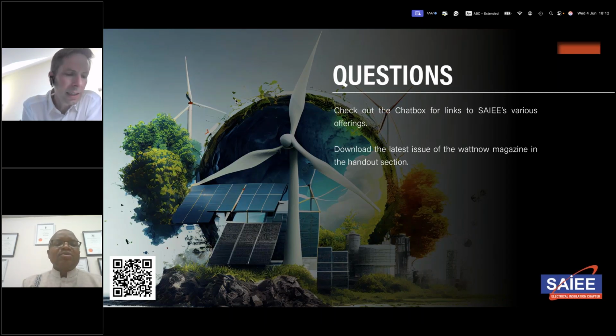Thank you. Then there's a question. Maybe at this point I can give you the perspective from the European Union. There is a new regulation in the European Union which clearly states a phase-out plan. Depending on estimations of market availability of different voltage level equipment for medium and high voltage, there are clear dates set where new equipment cannot be SF6 anymore if there's more than one vendor with a non-SF6 solution available on the market. I think it's starting 2028 until 2035 is the last phase-out date for the last voltage level.